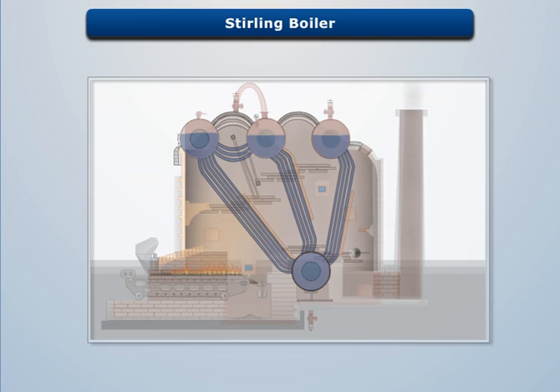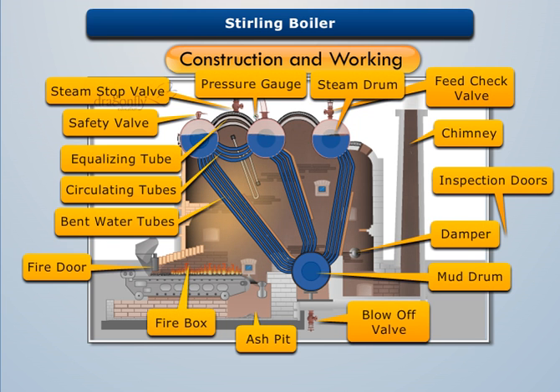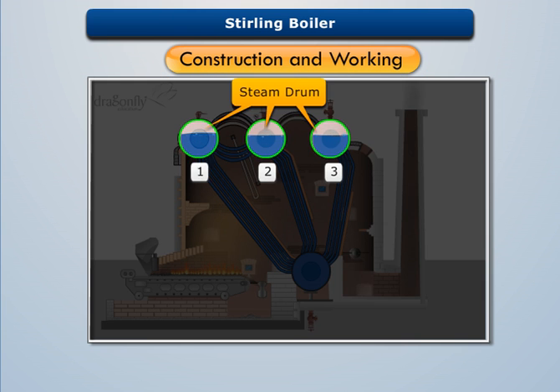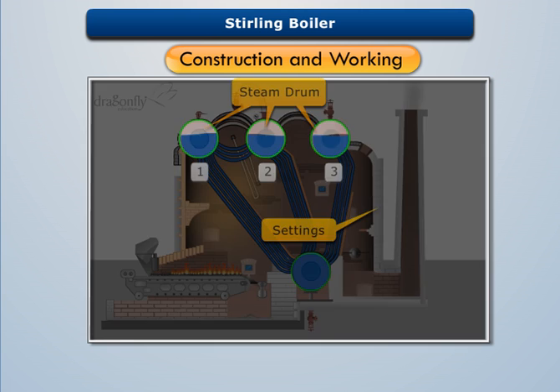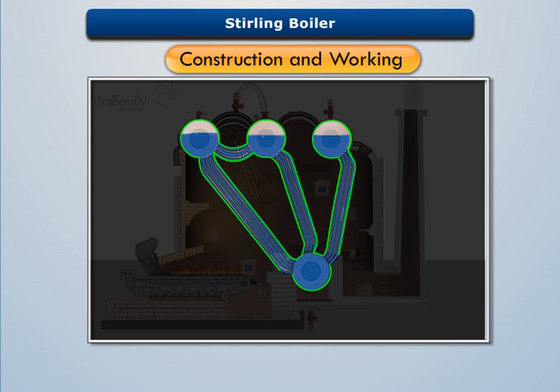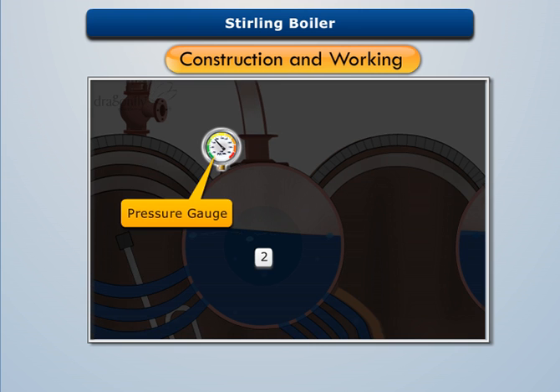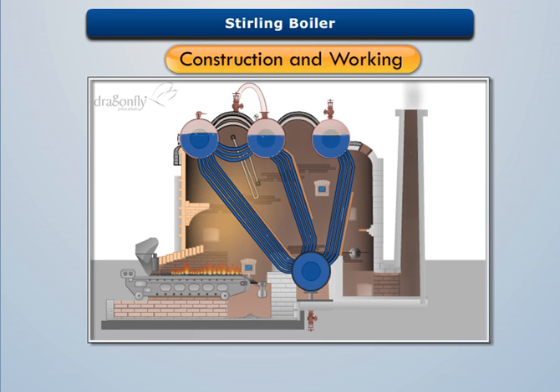The Stirling boiler consists of three straight horizontal steam drums arranged in the upper part of the boiler settings and a mud drum arranged in its lower part. The steam drums are connected with the mud drum by a series of bent water tubes. Steam drum one is attached with the safety valve, drum two with a pressure gauge, drum three with a feed check valve, and the mud drum with a blow-off valve.